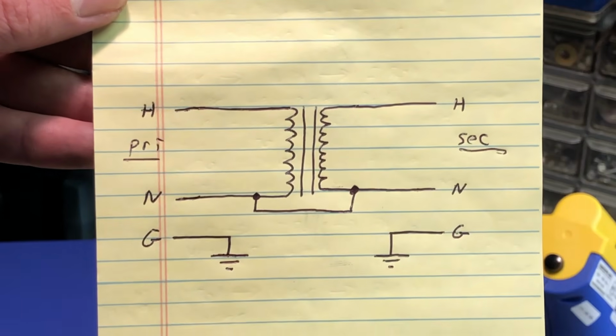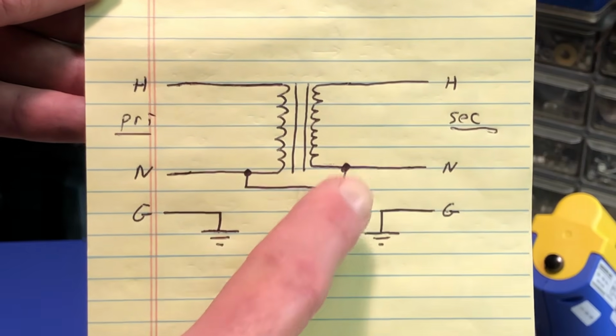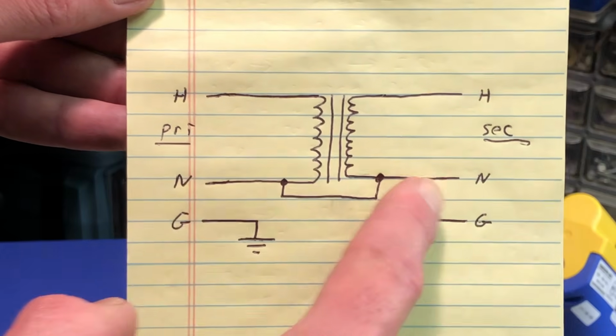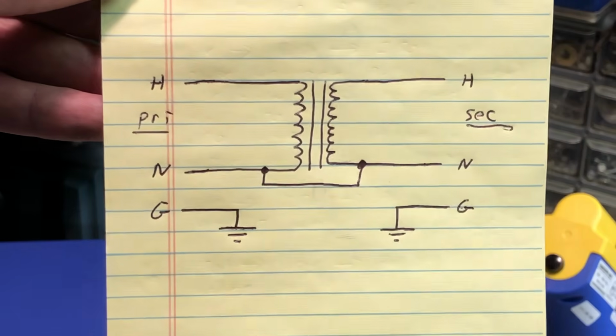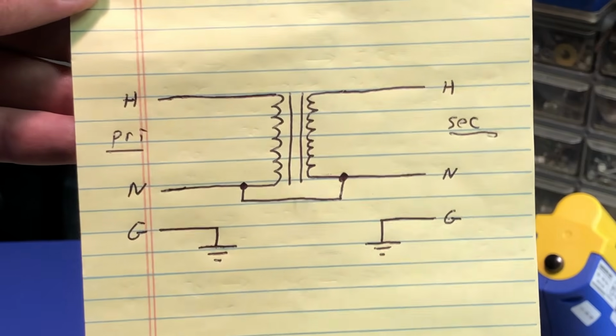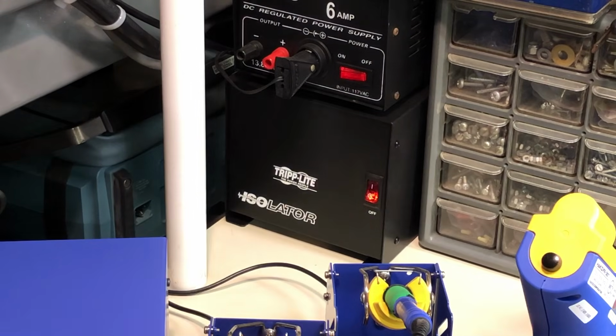And this link needs to be removed so that there is complete electrical isolation on this side and no connection to the primary. Now, the manufacturer puts this link in here to tie the neutrals together really for a safety reason, because this is intended to be used with consumer electronics, stereo equipment, amplifiers, things like that. It's really intended as produced by the manufacturer as a way to eliminate noise, issues like that with the AC line, and they wanted the neutrals connected together. But when you're testing the vacuum tube equipment that I previously mentioned, you want complete electrical isolation.